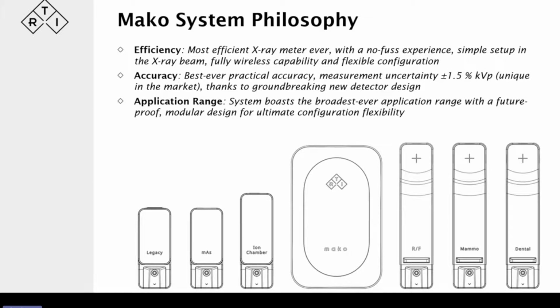The application range also is the best on the market, where we measure not only the traditional values like kV, dose rate, time, HVL, and total filtration, but with additional probes, we measure the CTDI, we can measure DAP, light, beam width, and CTs, etc. So the application range is the broadest on the market. And how do we achieve this? Well, we're building on the successes of 40 years that we have been in the market, and the successes we've had with systems like Barracuda, launched in 2000, the Piranha, the first generation, launched in 2009, as well as Cobia and other products along the line.